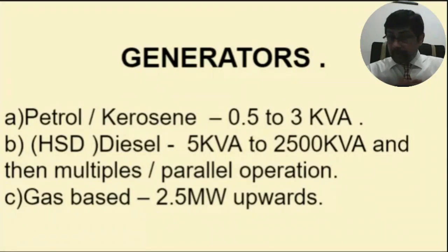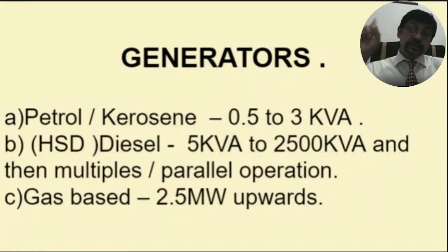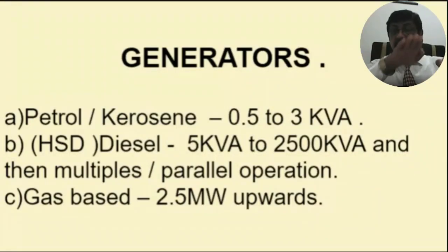So we can go for parallel operation. Now, what is parallel operation? Parallel operation is when you have a total requirement of, let's say, 3000 kVA for an industry, and in 3000 kVA you have 1500 kVA one generator and 1500 kVA second generator. Now what happens in case the first generator is totally loaded with 1500 kVA, then this parallel operation circuit or parallel operation arrangement will give command to the second generator to start, and the second generator will come in the picture, and these two generators will share the load between them.